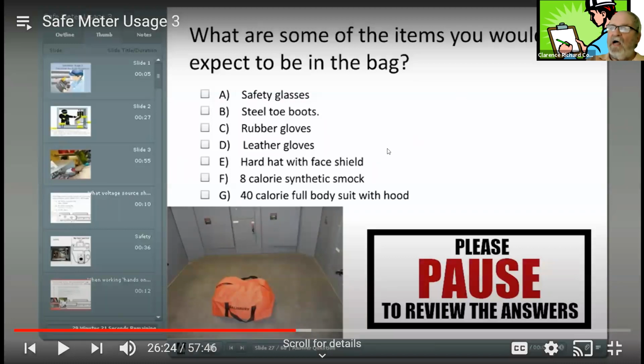So the things that could be in this bag are safety glasses, steel toe boots, rubber gloves, leather gloves, a hard hat with a face shield, 8 calorie. It says a synthetic smock. You don't want a synthetic smock. It's got to be a Nomex cotton one. All these things should apply except for that one there. A 40-calorie full body suit with a hood, you can see that as a requirement, but that just really isn't used. So I would say an 8 calorie Nomex one is the kind you want. And it isn't cumbersome at all.